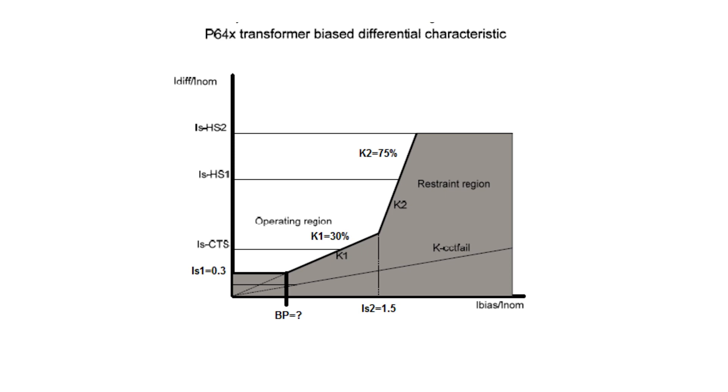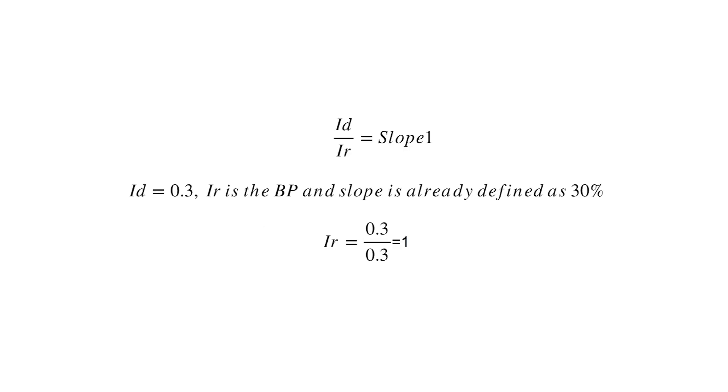To identify BP, let us use the formula ID by IR equals slope 1. ID equals 0.3. IR is the BP and slope is already defined as 30%. IR equals 0.3 divided by 0.3 equals 1.